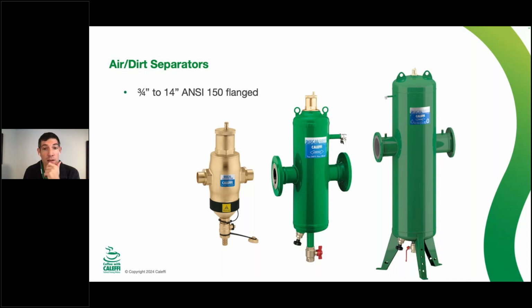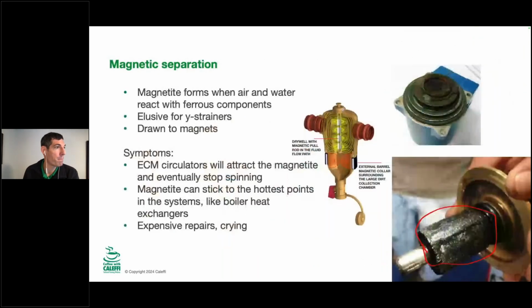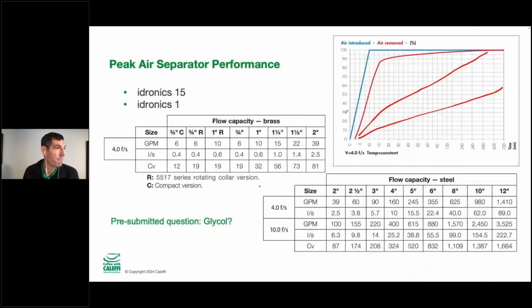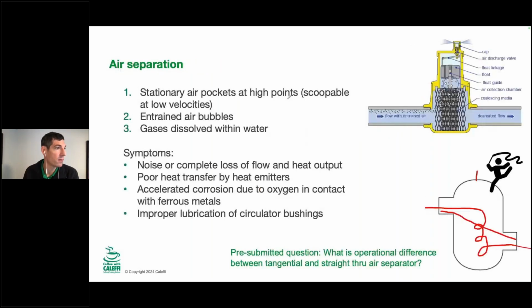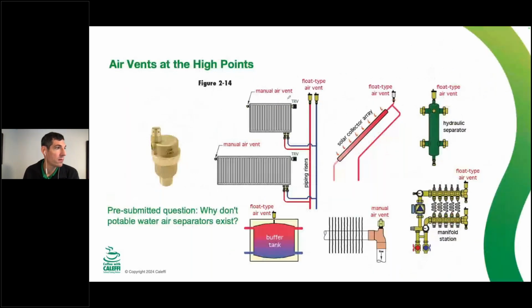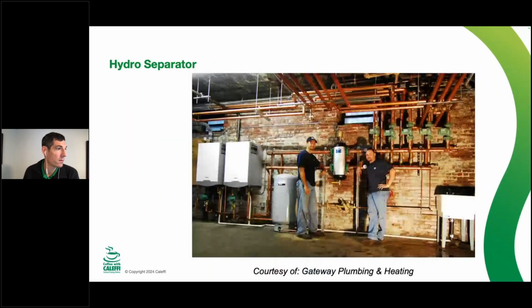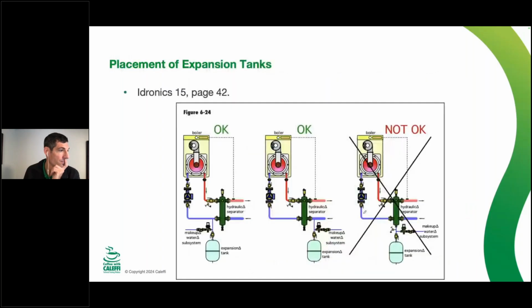And that's a good question. That's a good one. Yeah, and yes, in fact, it can. But if that's happening, you've got a subatmospheric condition in your piping. If you've got a picture, one of them here. Let's see if I can go back. Usually what causes that to happen, when you have a job where you've got a chronic air problem and every plumber in the city has gone over and bled the system out and they still have air problems, you're probably pulling air in through an auto air vent.